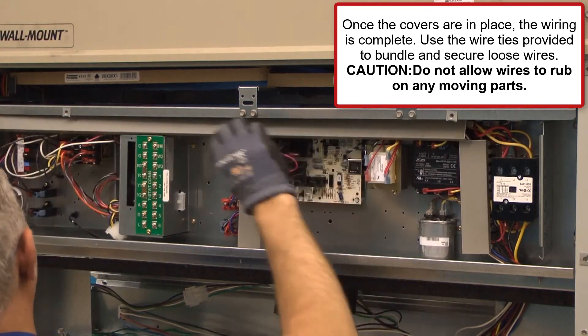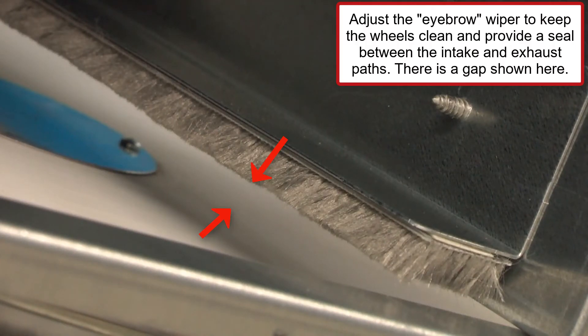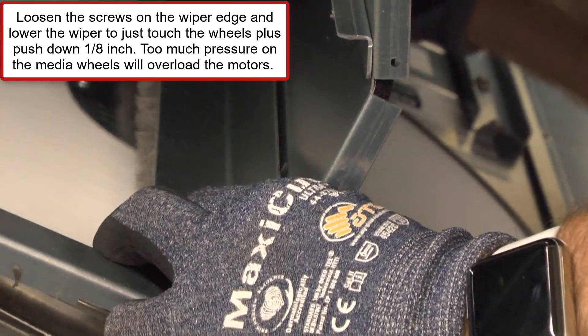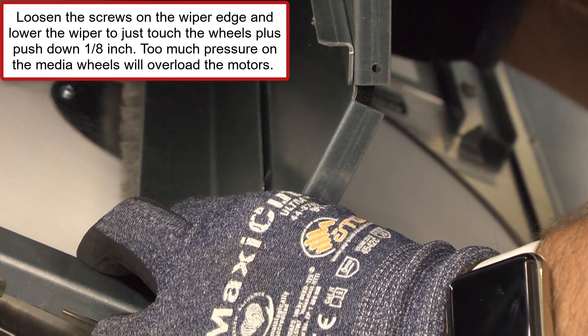Next, adjust the eyebrow wiper to keep the wheels clean and provide a seal between the intake and exhaust paths. Loosen the screw on the wiper edge and lower the wiper to just touch the wheels plus push down 1/8 inch. Too much pressure on the media wheels will overload the motor.